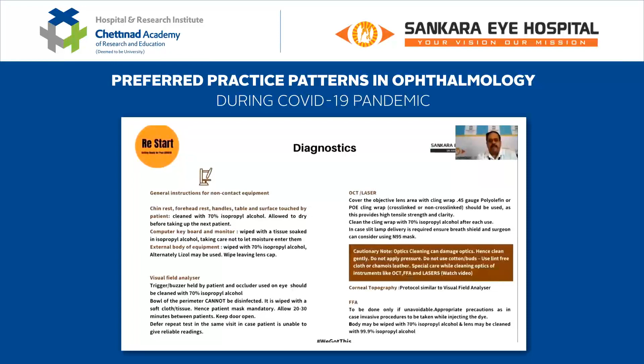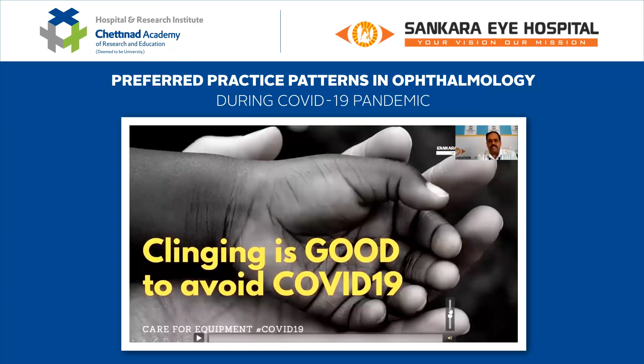For the OCT and laser, we've come up with an innovation in terms of how we can protect it. I'll run you through a short video. Essentially, we use a cling wrap to cover it, and that can be wiped down. FFAs you do only in cases where it is unavoidable. The body and the lens can be wiped with 70% isopropyl alcohol. For your auto-ref, your NCTs, and if you have an optical biometry, you can only clean the body with 70% isopropyl alcohol. The lens should not be cleaned, so that is something you have to be very careful about. This video has an inbuilt voice as a part of it. It just shows you what we've done to protect our OCTs and laser. I'll just play this short video now.